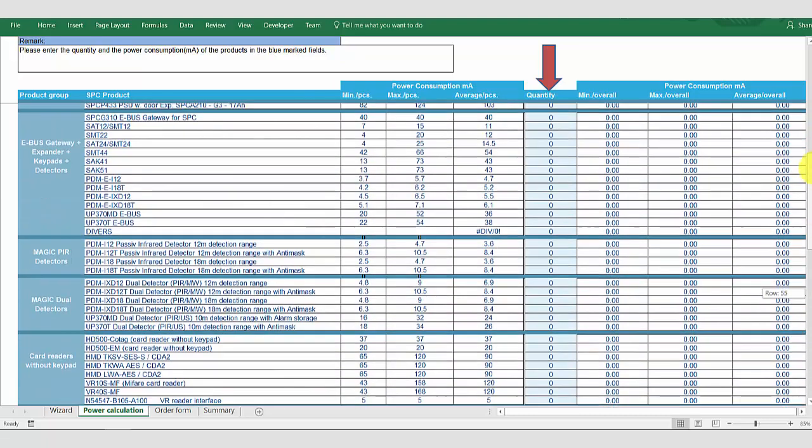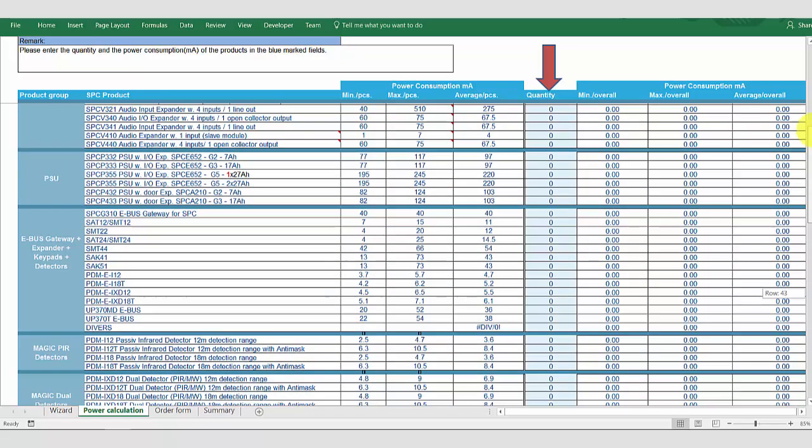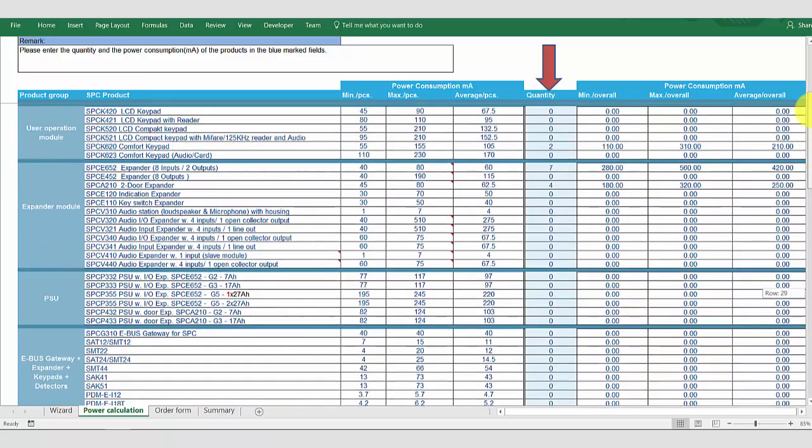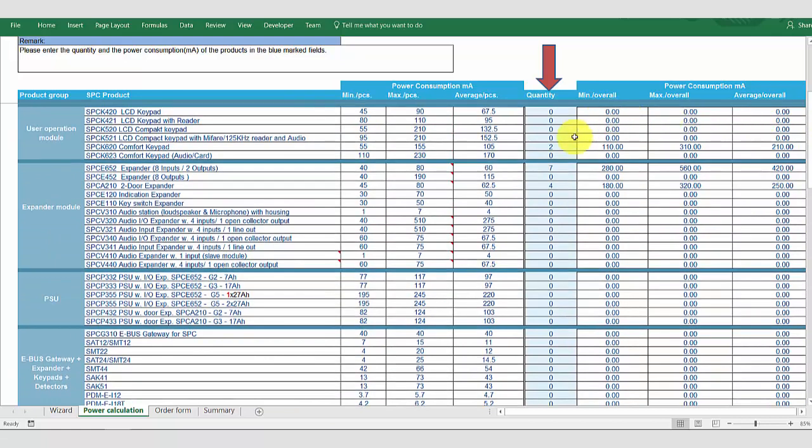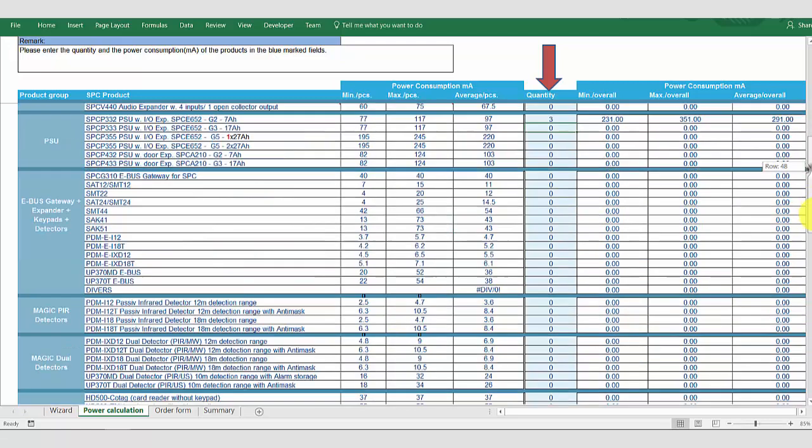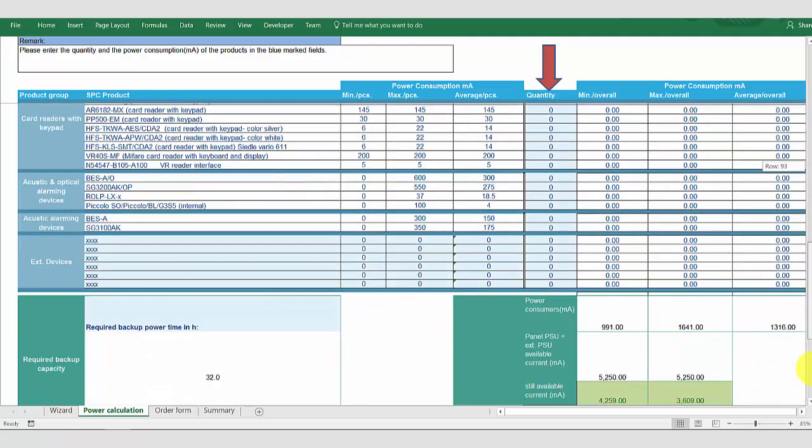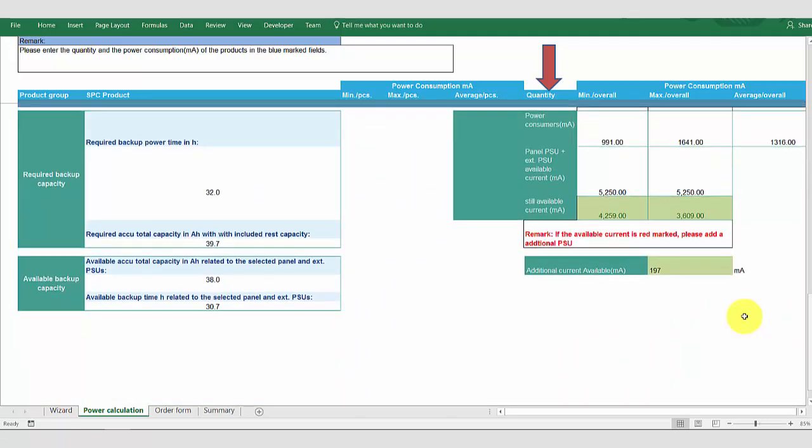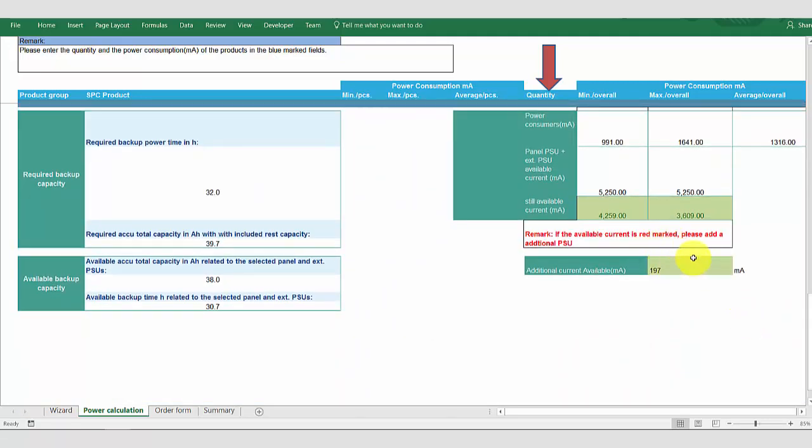In order to address this, we will replace some of our standard input expanders with power supply expanders. So, I'm going to insert three power supply expanders. We now have sufficient power in order to power the entire system.